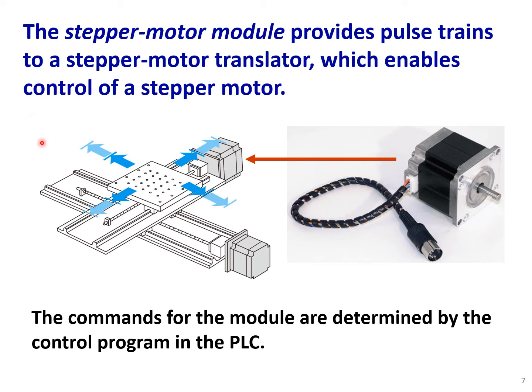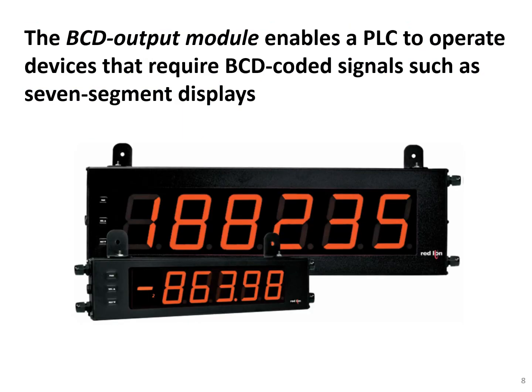The stepper motor module provides pulse trains to a stepper motor translator, which enables control of a stepper motor. It is a user-specific module for the stepper. The commands of the PLC are determined by the control program. The BCD output module, or binary coded decimal output module, enables the PLC to operate devices that require BCD coded signals, such as seven-segment displays. To change the setting of these displays, we need a BCD output module.